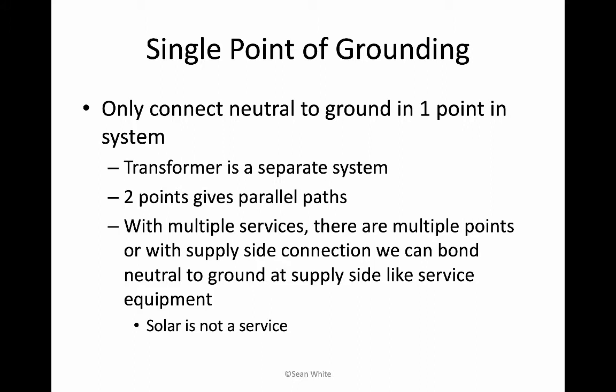This is not a hands-on course. But anyway, just in case you did that anyway, if you took off the cover of your main service panel and you opened it up, you can look in there and you can see a place where there are green wires and white wires going to the same bus bar, the same connection point, and that would be your single point of system grounding. That's where your neutrals or your white wires are connected to your grounding wires or your green wires. So on that bus bar in there, you'll probably have one wire that's going to your electrode. That's the grounding electrode conductor, the GEC.